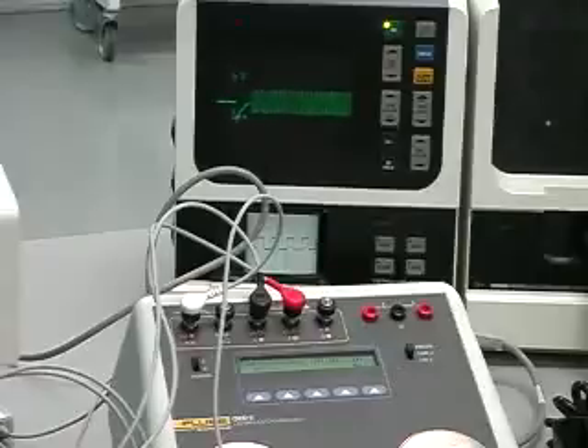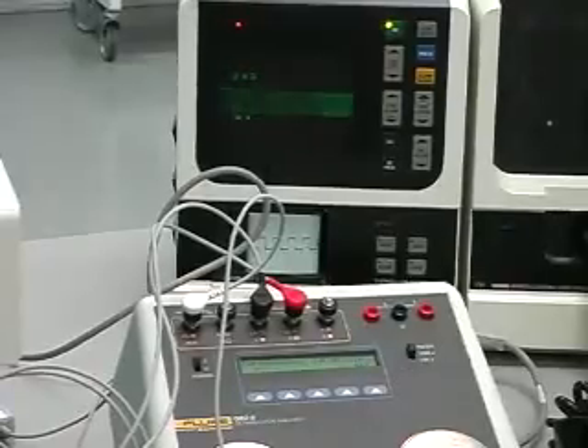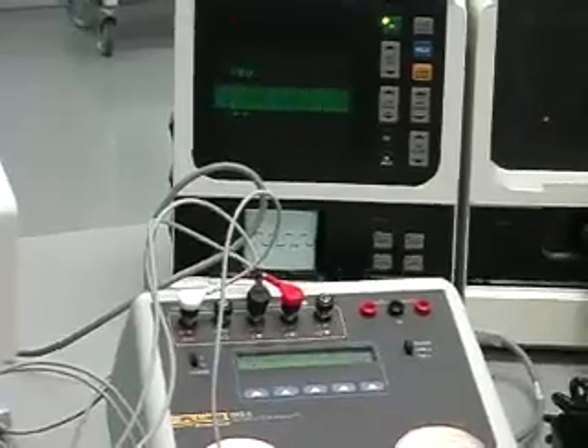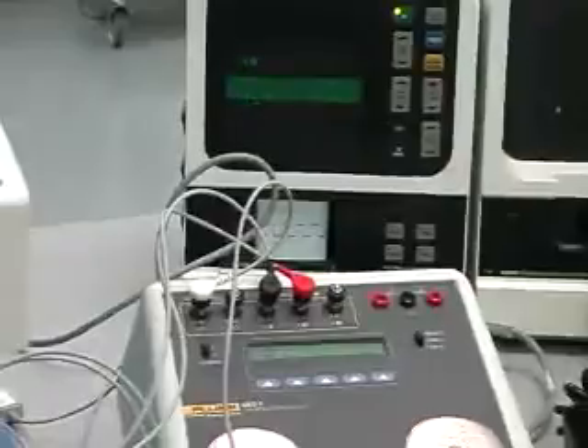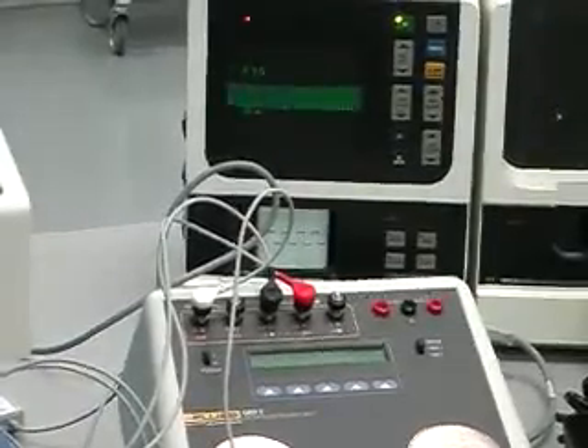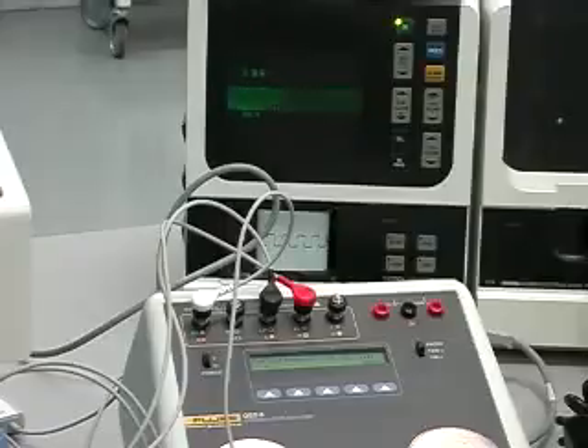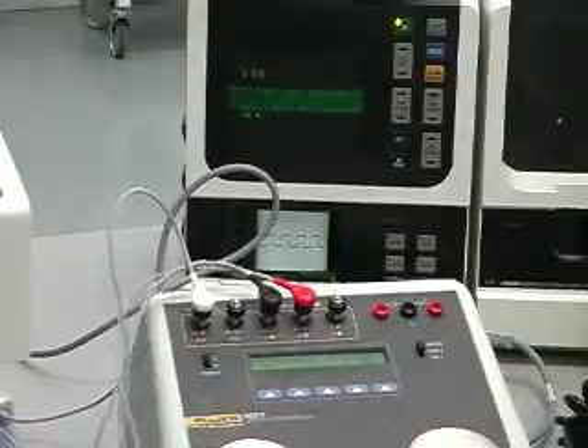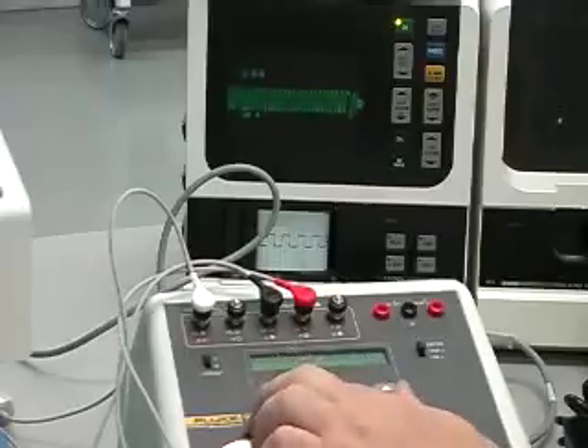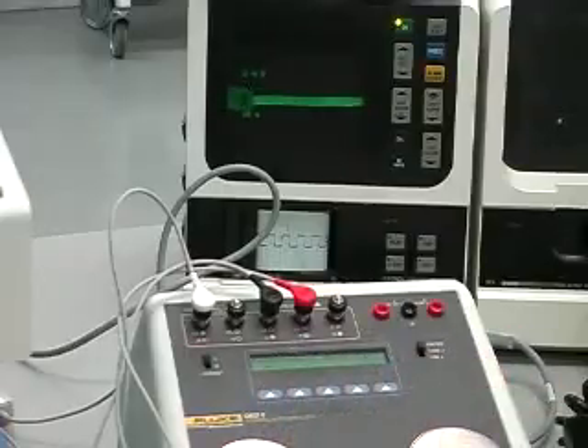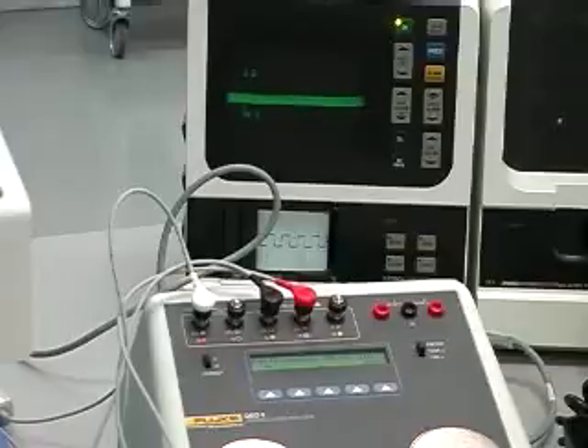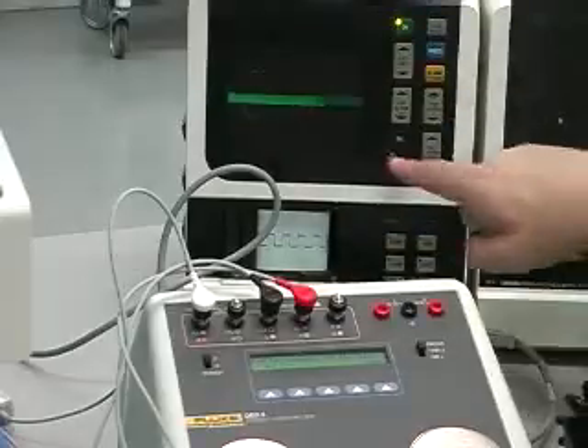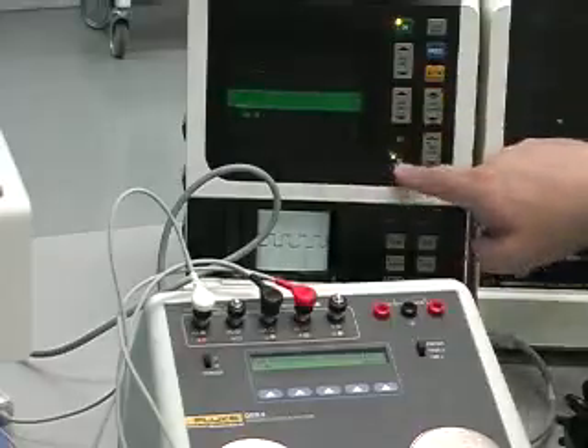And then bandpass testing, looking at either diagnostic mode or your monitoring quality mode. 10 hertz should come through at a millivolt. So 10 hertz, that's where a lot of your ECG data, your waveform content, does exist, and that response should be relatively flat. 40 hertz, typically a 3 dB down point for your monitoring quality on your monitor, so you can see the response is greatly reduced. So you can barely see any of that component, even at the faster sweep rates.